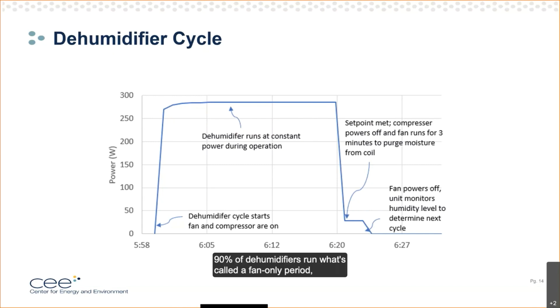90% of dehumidifiers run what's called a fan-only period, or maybe you might call it a purge cycle, after the main cycle. It usually runs for about 3 minutes. There's no dehumidification in this time, but it might serve two purposes, and manufacturers are not exactly straightforward about this. One purpose is that it's sort of an easy interlock that prevents the compressor from starting up again too quickly. Extreme short cycling of compressors can damage them. But the main purpose is probably to clear moisture off the evaporator.